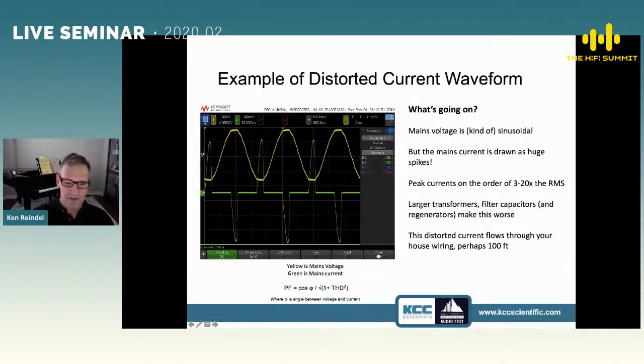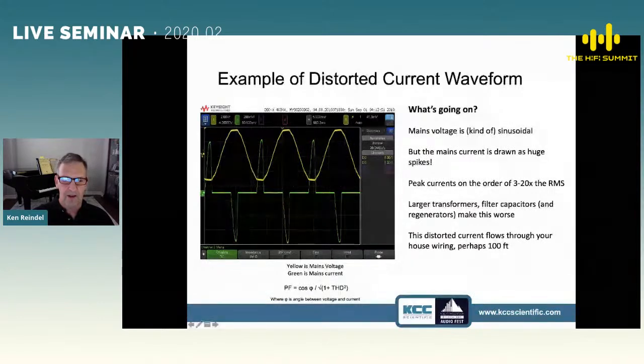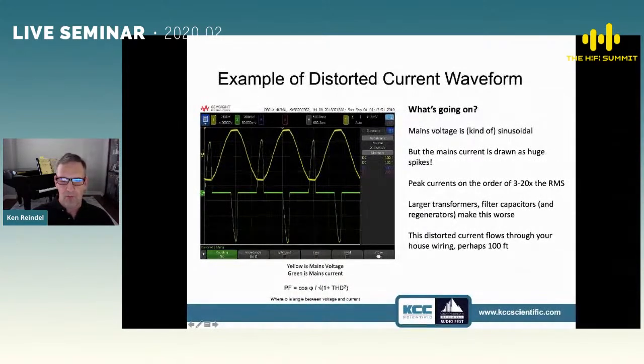And you could see the equation here for power factor is, basically here's the relationship between the voltage and current, that's the angle, and this is the total harmonic distortion of that current. So as this distortion goes up, power factor goes down. Ideally, 1 is what you want. 1 means it's linear. As you get away from 1, that means you have more total harmonic distortion on that line, and it's going to present itself as noise, and it's getting into places that you don't want it.